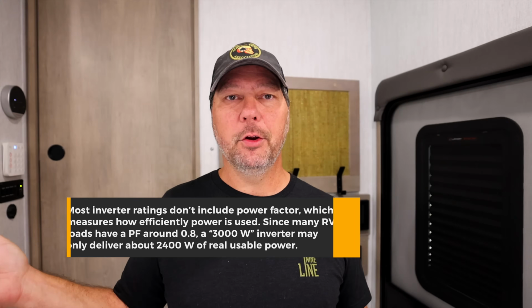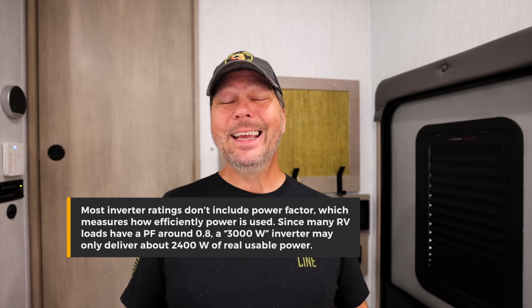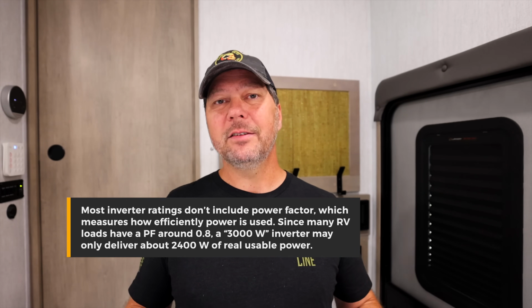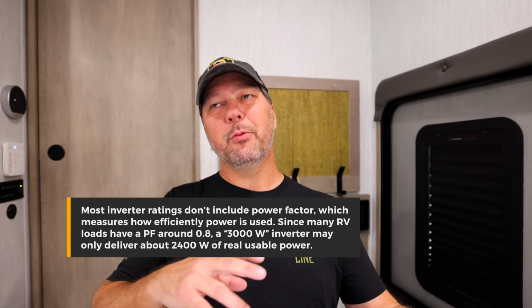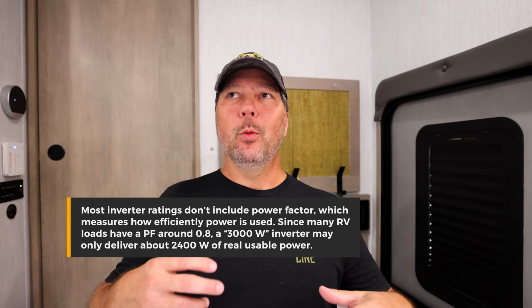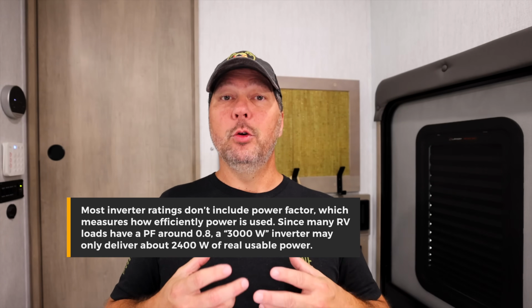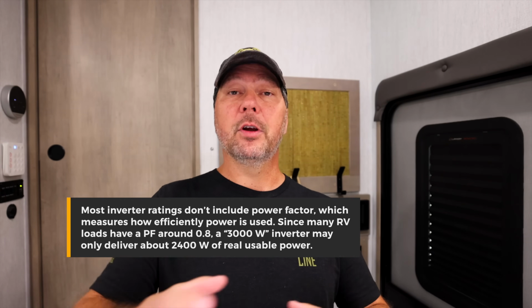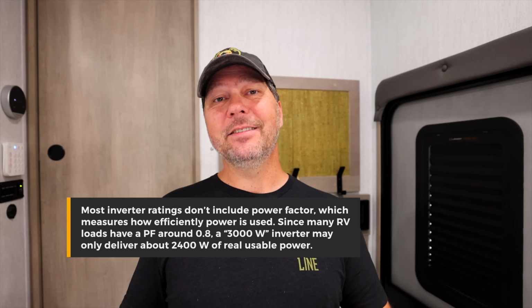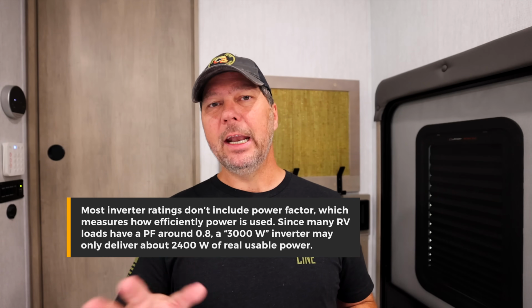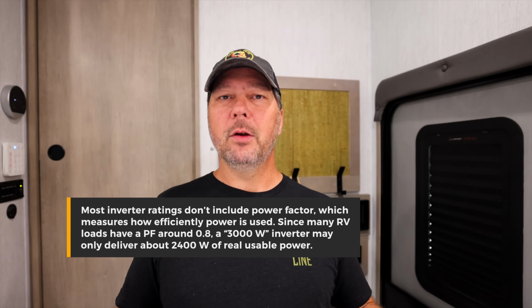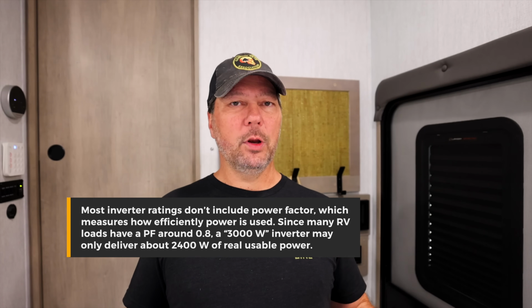If you're familiar with inverters, these are no different than Victrons and everybody else's. Even though it's rated at 3,000 watts, that's a little misleading because it's really 3,000 volt amps, and what you're not seeing there is that you lose some energy during the conversion process from DC to AC. You're lucky to get probably 80%, so really a 3,000 watt inverter is going to give you about 2,400 to 2,500 watts of real power. But you still got plenty of energy on each line to run all 3 ACs.